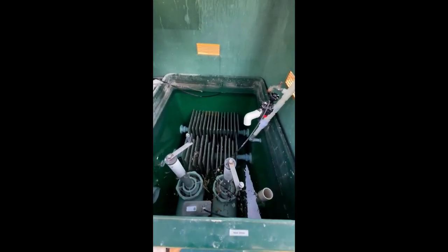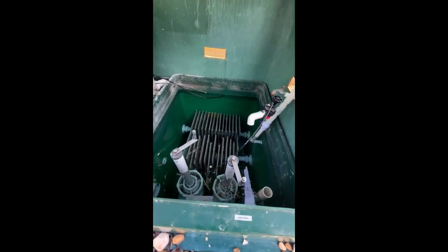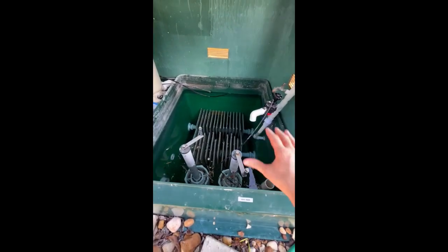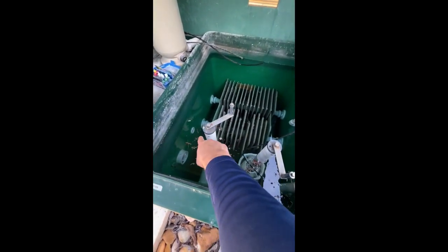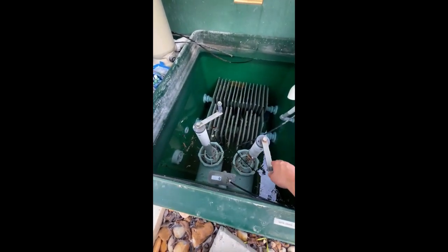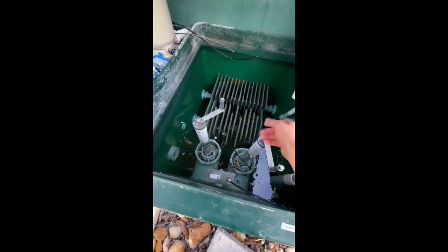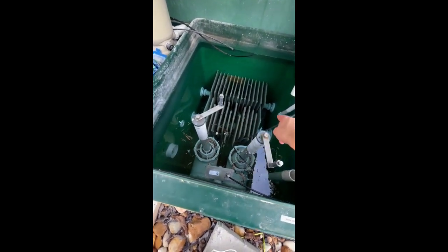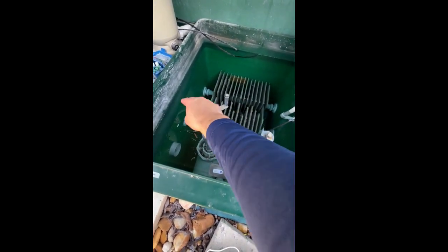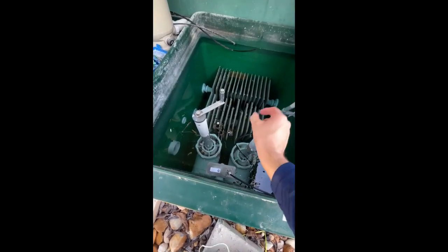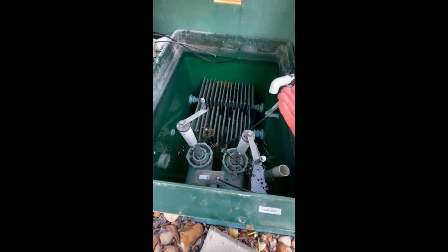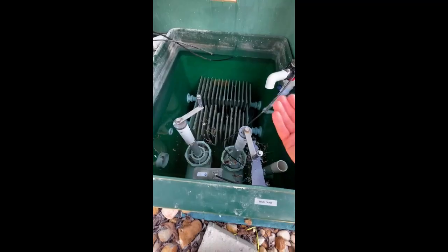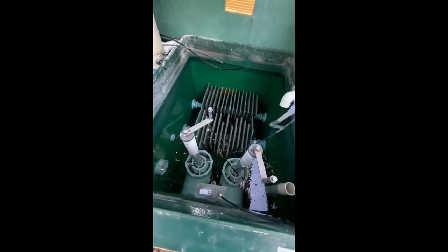I want to introduce you to the components that every single commercial pool will have. Always start here in the surge tank. Water comes in through here, main drain gutter, 70% from the gutter, 30% from the main drain. Passes through the DE filters. There are holes underneath each of the grids. How many are there? 1, 2, 3, 4, 5, 6, 7, 8, 9, 10. Call it 12 holes right directly underneath the grid. Okay? They pass through there. The DE, the diatomaceous earth, it cleanses the water. It filters the water. Passes through there.